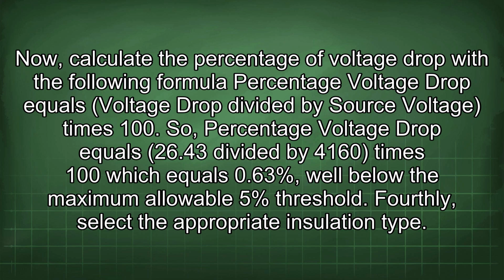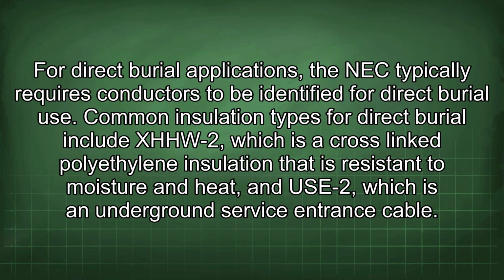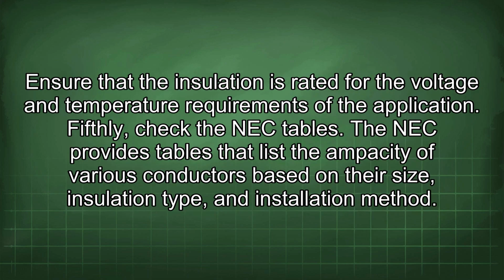Fourthly, select the appropriate insulation type. For direct burial applications, the NEC typically requires conductors to be identified for direct burial use. Common insulation types for direct burial include XHHW-2, which is a cross-linked polyethylene insulation that is resistant to moisture and heat, and USE-2, which is an underground service entrance cable. Ensure that the insulation is rated for the voltage and temperature requirements of the application.